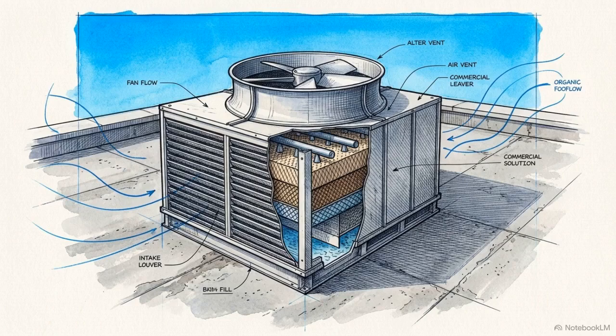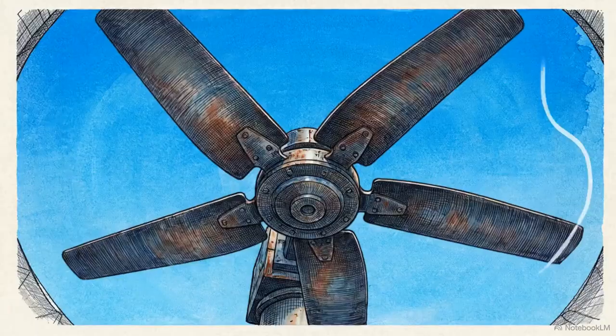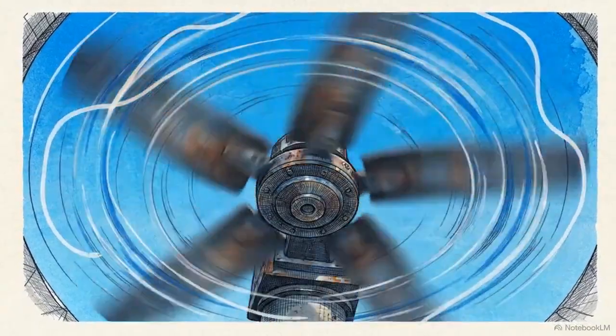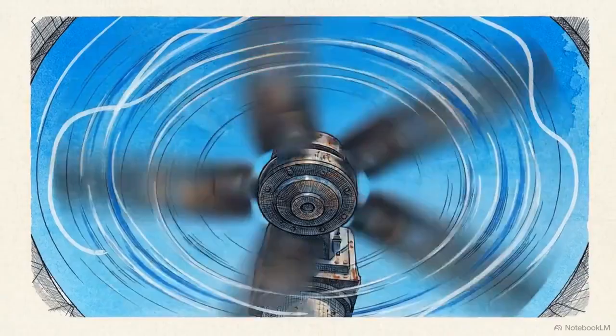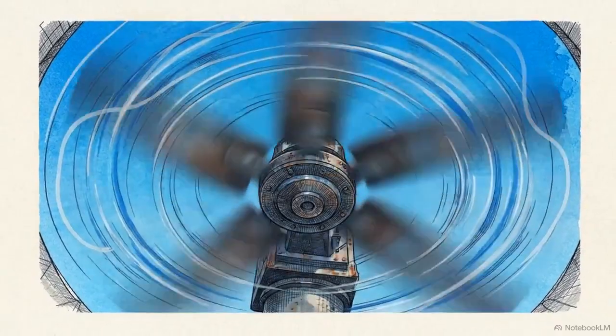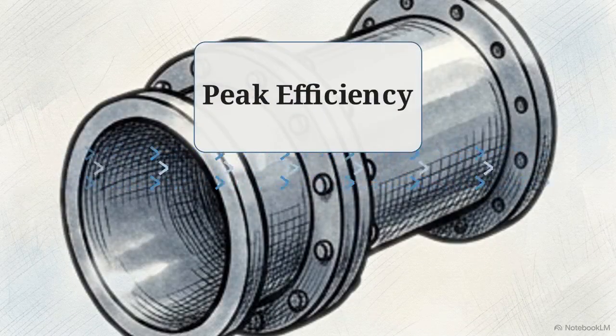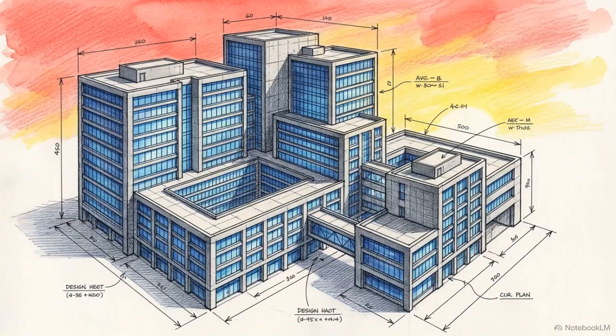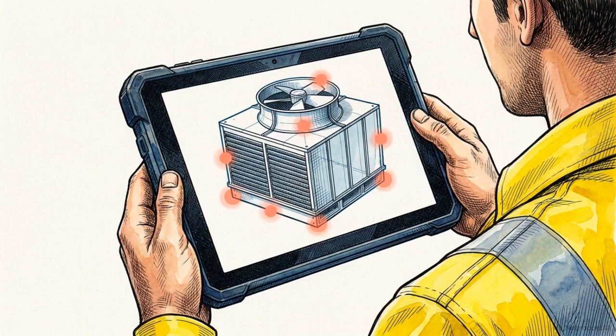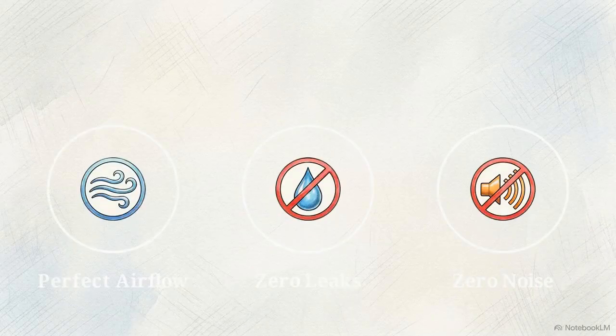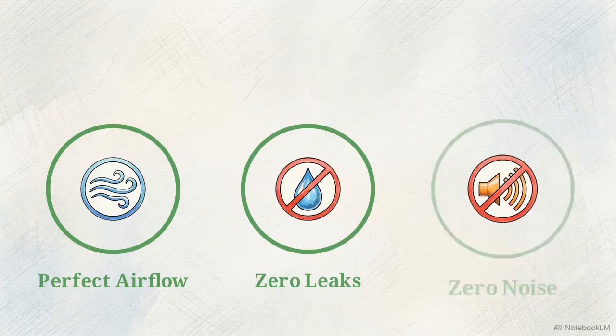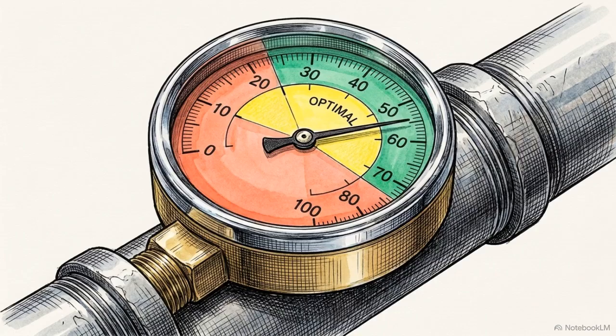Welcome to our first module on the physical installation of an HVAC cooling tower. Think of the cooling tower as the lungs of your HVAC system. If you install it incorrectly, it directly leads to catastrophic chiller failure. But get the installation right, and you secure peak efficiency and a long operational lifespan for the entire facility. In this module, we will walk through the 5 essential steps to achieve perfect airflow, 0 leaks, and 0 noise complaints. Following this precise sequence prevents system failure and guarantees maximum heat rejection capacity.